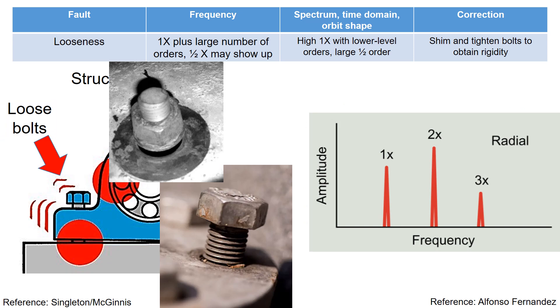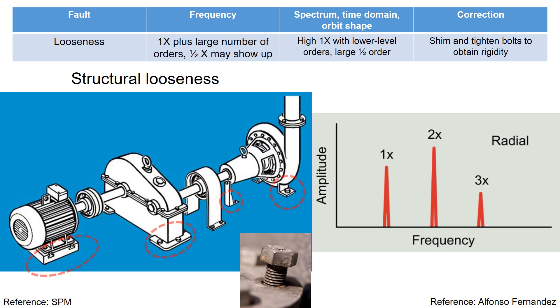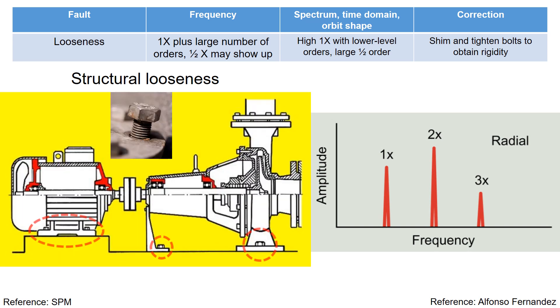Structural looseness can result in elevated vibration at frequencies such as 1x, 2x, 3x, and beyond. Indeed, it is crucial to examine structural looseness when there is a noticeable upward trend in the frequency spectrum over time. So, conducting a thorough inspection of the base bolts is essential.